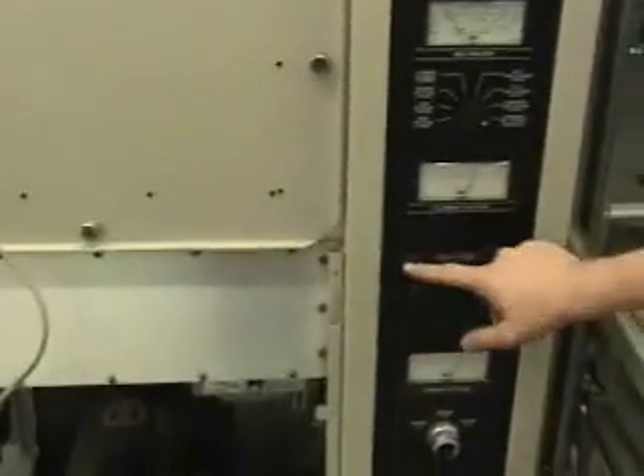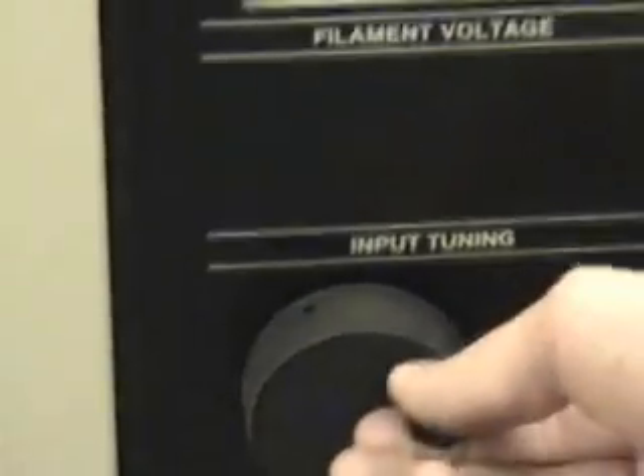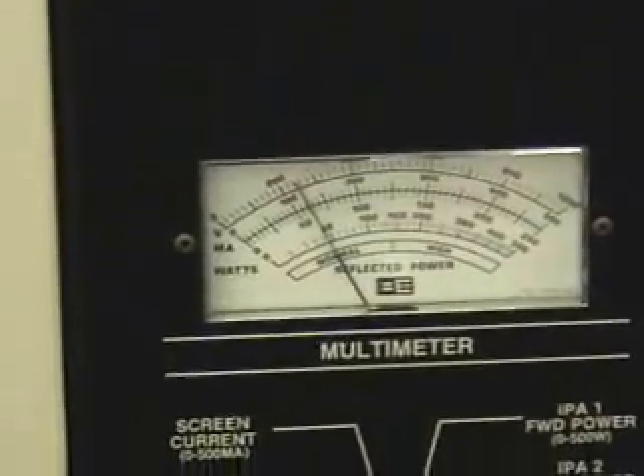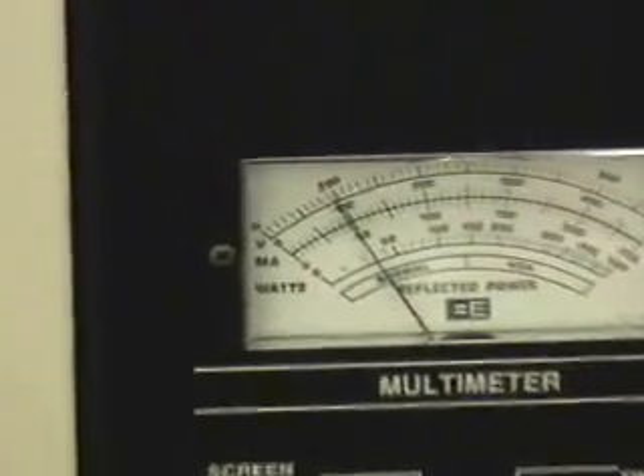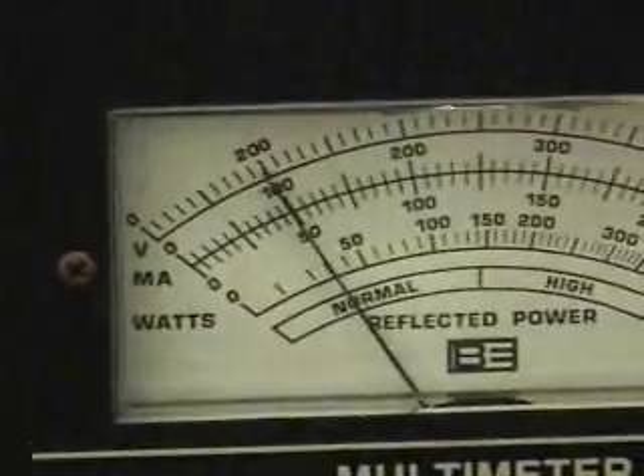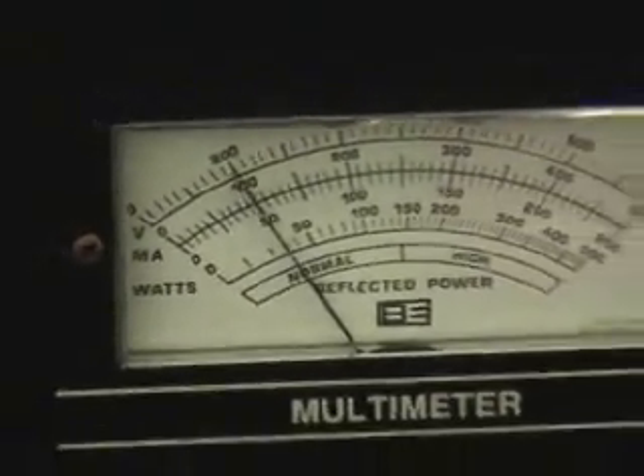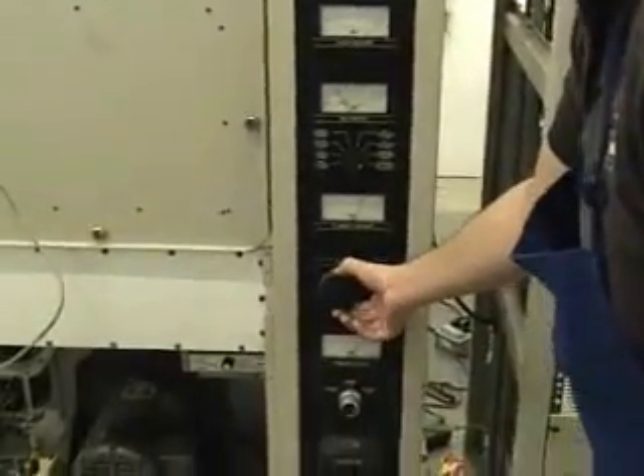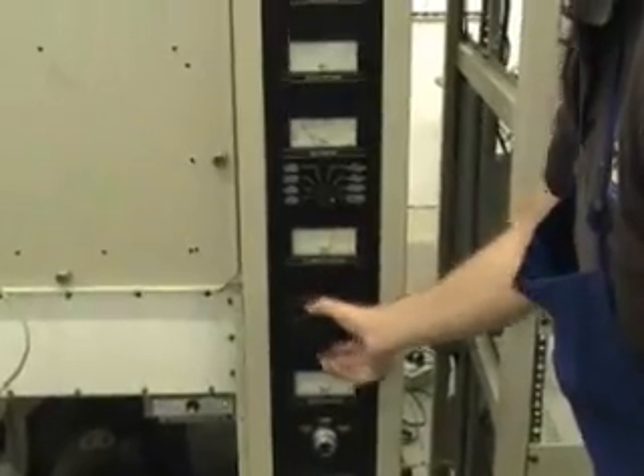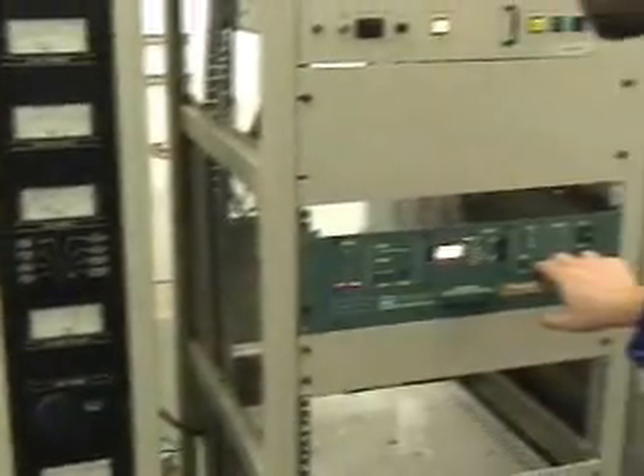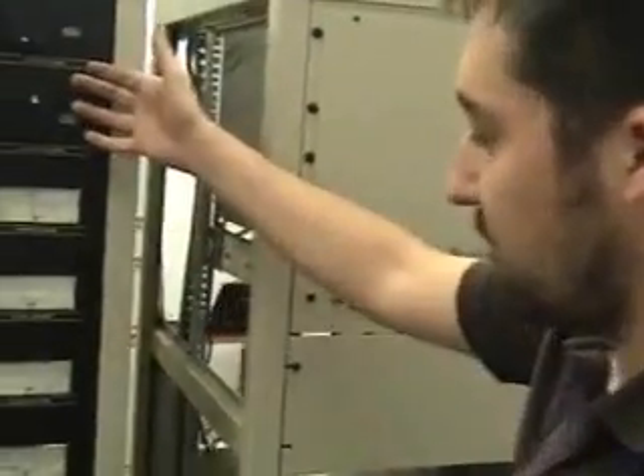To tune the IPA, the input, the grid, we have an input tuning here. We're simply going to turn it. We can see that this transmitter is already tuned up. You're just going to tune for a dip. As the transmitter comes up in power, this is going to change. So, as you tune, come up slowly, and you're going to be adjusting your input and tuning your transmitter.